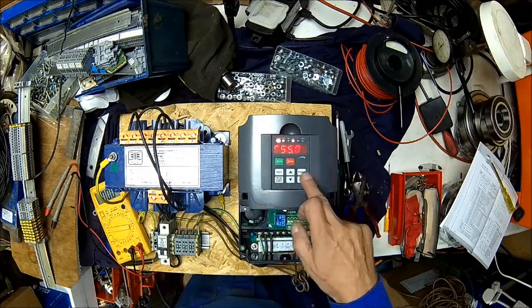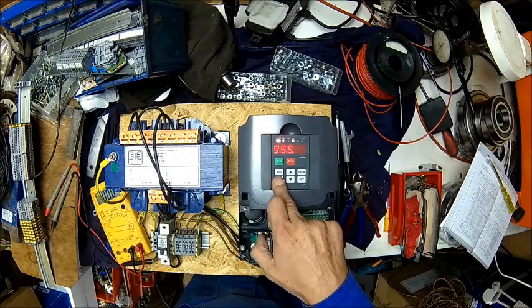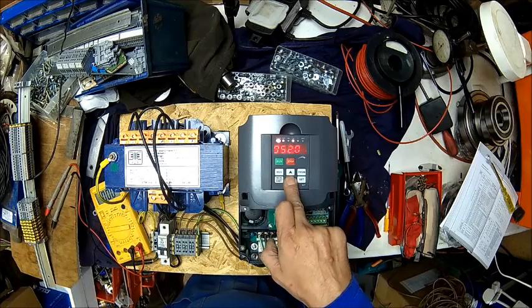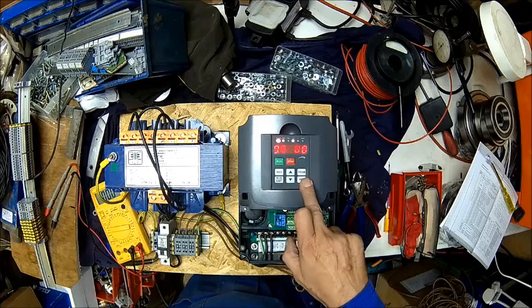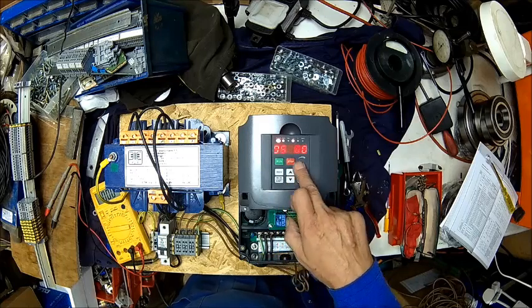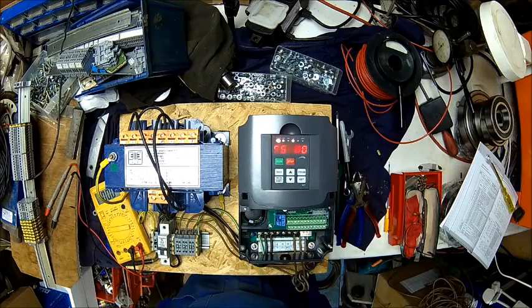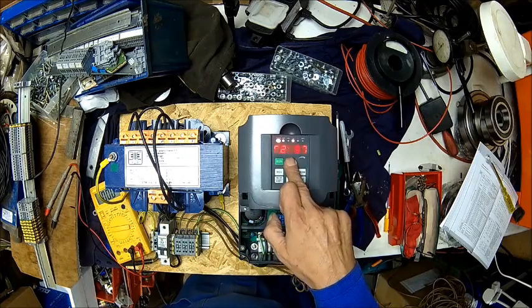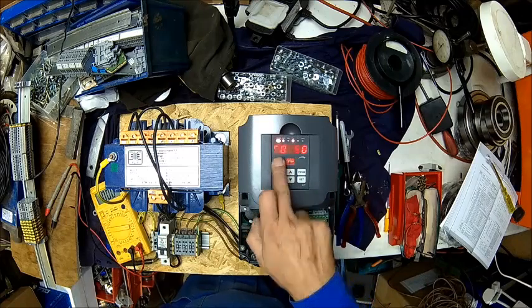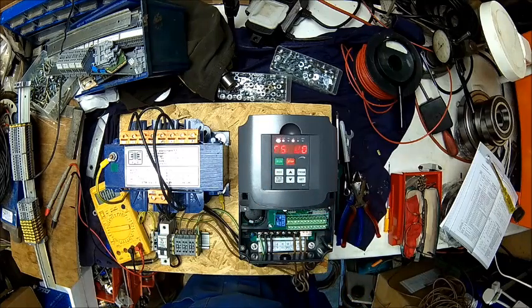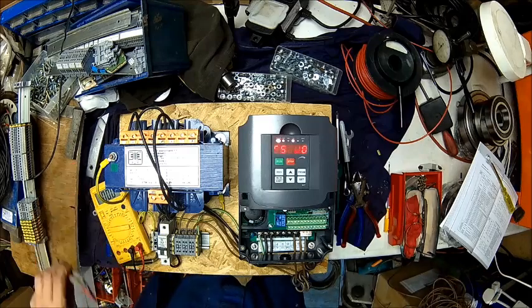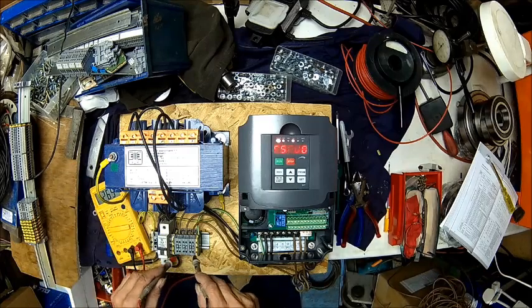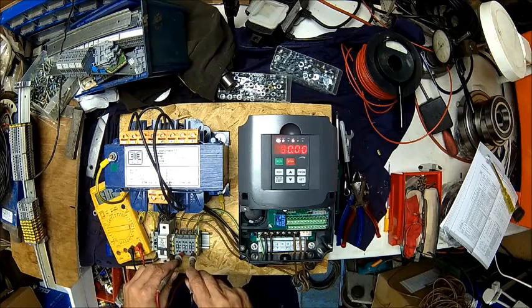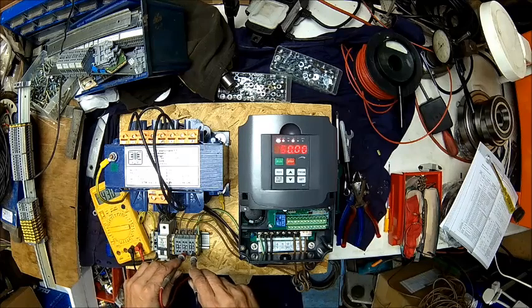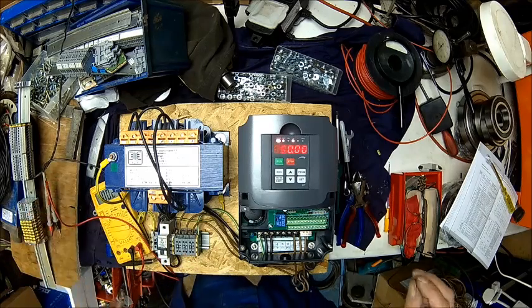We're running at 55 Hertz. We put that down a little bit. Make that 50. And run. Stop. Run. Yeah, 50. So we should have 415 volts on our output terminals, about. At the moment we're measuring garbage because there is no load on it. You can hear the... We need to put some load on so you can check the voltage.